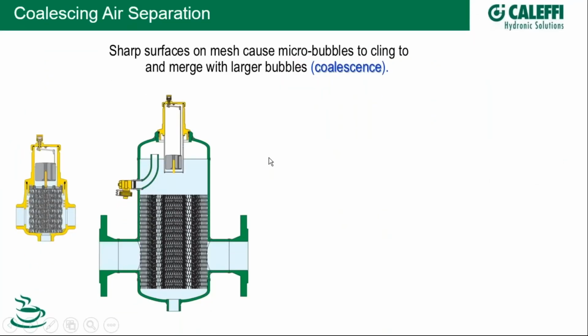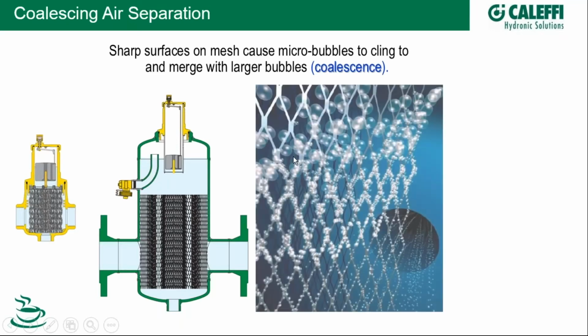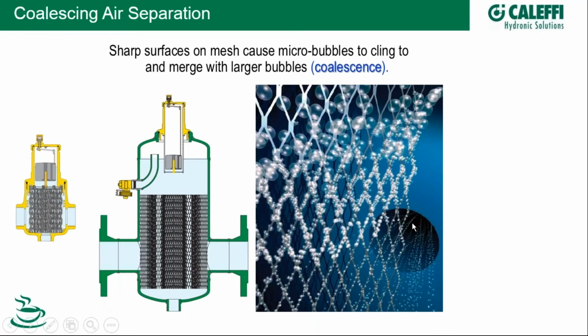The biggest problem with air is corrosion, quite frankly, and secondarily, probably noise in certain hydronic systems. So manufacturers like Caleffi have coalescing air separators. What is coalescing? It's the process of taking advantage of microbubbles being created coming off of a boiler, for example, or even on the return leg back to a chiller after it's given up its heat in your terminal units, and collecting that air by way of adhesion. Those microbubbles adhere to these sharp surfaces inside the separator. Those small microbubbles collide, creating a bigger bubble, but they continue clinging until eventually the buoyancy force from the larger bubbles overcomes the static cling force against the mesh. Then they float up into the chamber, and the float opens the linkage and out goes your air. That's how air separators work.